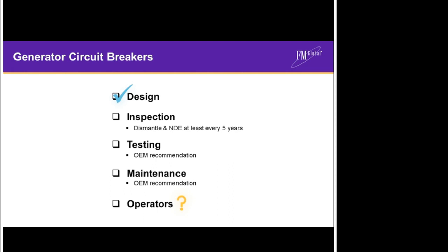to OEM recommendations. What differentiates the electrical isolation from the steam isolation is the impact of operators. When it comes to steam, the intervention generally needs to be so quick that the operator doesn't have time to intervene in an appropriate way. However, when it comes to motoring events, the operator almost always has an opportunity to take action to reduce the impact of a motoring event. However, this generally requires the formulation and training on appropriate motoring response plans and operators having the authority to act appropriately.